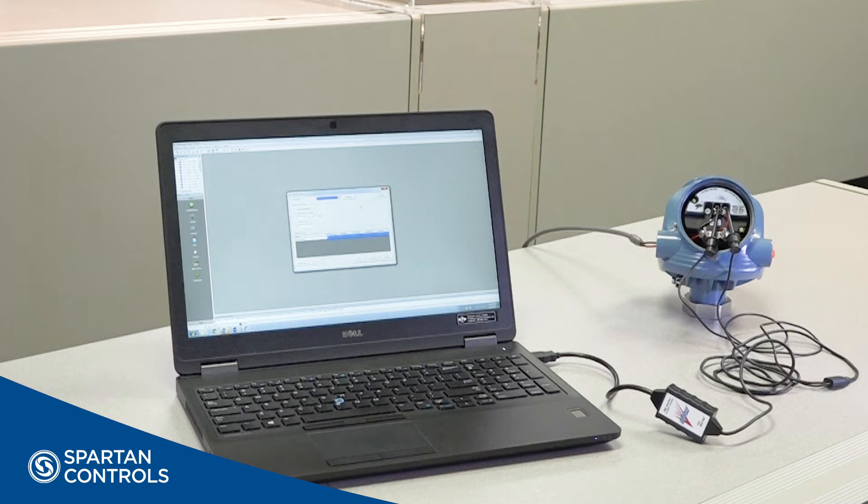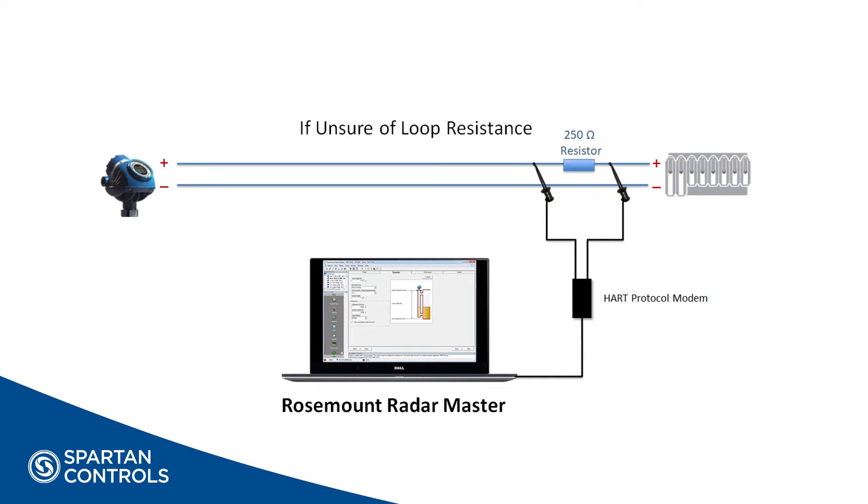To establish a connection with the device in the field, you will require an interface modem. The transmitter we are using in this demo is HART enabled, so we will use a USB HART Bell 202 modem. Spartan Controls offers both USB and serial modems for any protocol you may require. As with any HART enabled device, you can connect at any point on the two-wire trunk provided there is at least 230 ohms of loop resistance. If you are not sure whether or not you have enough resistance, it is good practice to temporarily install a 250 ohm resistor in series and clip your HART leads on either side of the resistor.